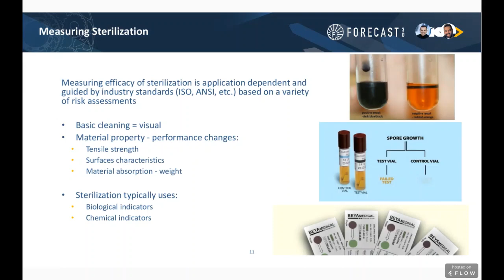The other aspect of this, if you dive a little bit deeper, is the actual material property and performance changes. So if you were to go through a sterilization cycle, how does it actually affect the part that you're working with? Again, metals, it's typically not as much of an issue, where plastics it is. And then the typical case for most sterilization, where there's more extreme conditions and requirements and risk assessments in play, you're going to see biological indicators and chemical indicators. And the idea there is that you will be able to identify if there's some sort of microorganism potentially growing there, or that a certain chemistry is reacting the way that is approved by those industry standards.